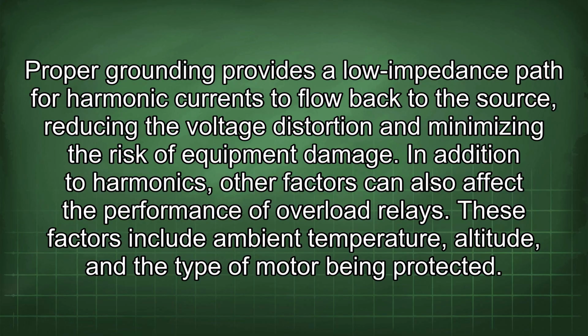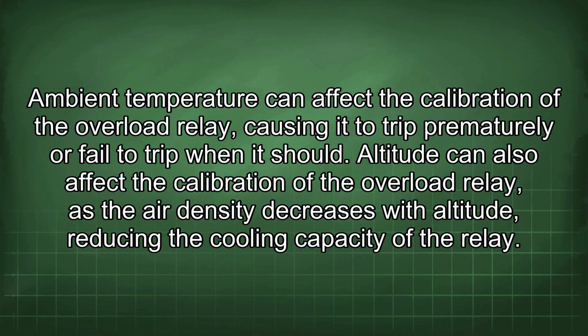In addition to harmonics, other factors can also affect the performance of overload relays. These factors include ambient temperature, altitude, and the type of motor being protected. Ambient temperature can affect the calibration of the overload relay, causing it to trip prematurely or fail to trip when it should. Altitude can also affect the calibration of the overload relay as the air density decreases with altitude, reducing the cooling capacity of the relay.